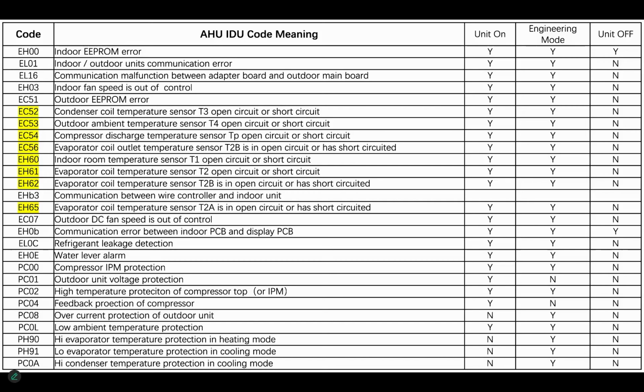We're going to go to PN, UV, and W. You're going to ohm with the power off and the compressor disconnected from the inverter. You're going to ohm between PN, UV, and W. So go P, N, UV, W, N, UV, W, all the way through. They should all be several mega ohms to open or infinity. If you get any reading that's like 2 mega ohms, I'm going to tell you the inverter's bad. Check it to ground. Same thing. Should be several mega ohms to infinity.